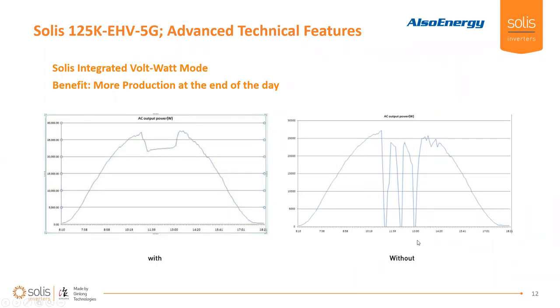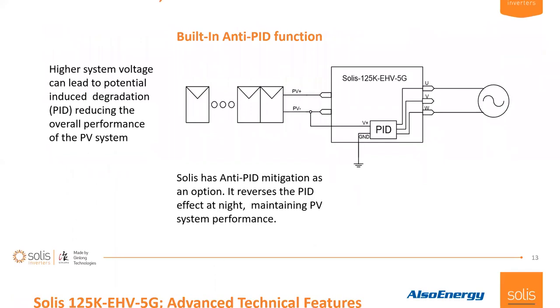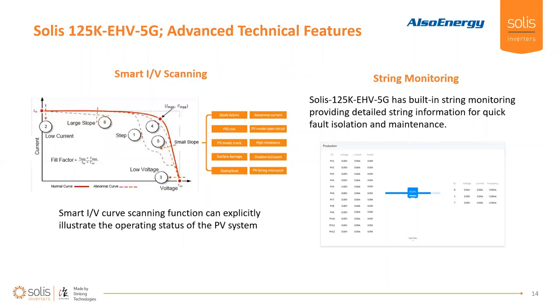Another feature we like to talk about is volt-watt mode — essentially an advanced ride-through function. You can see in that second diagram how the system drops out for five minutes here in the United States in each of those instances, whereas on the curve on the left you've got a lot more energy production at the end of the day. As we increase the voltage in these PV systems, PV modules can become more susceptible to induced degradation. Solis has been working on this anti-PID mitigation as an option — essentially reversing the PID effect at night to maintain the performance of all your PV modules within the array.